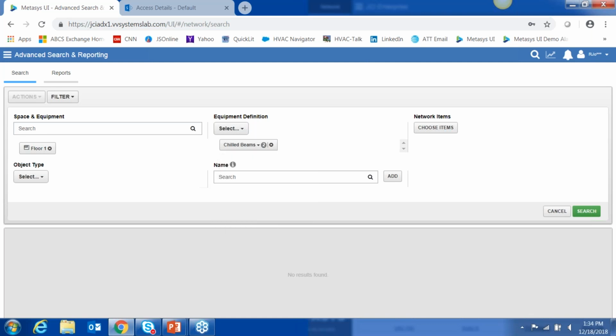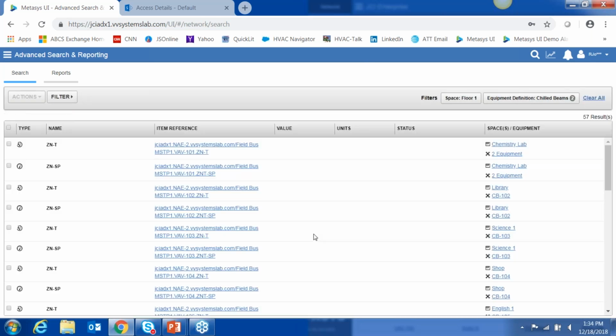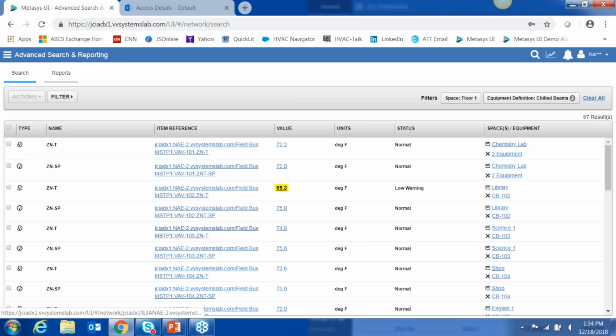Simply by selecting those filters and clicking the search button, a table quickly appears showing the requested information: the point name, the Metasys reference number—which if you're a savvy operator might be a little breadcrumb trail back to your old way of thinking—and the value of the point. If it's in a non-normal status, there'll be a color code indicating maybe an override, above a limit, or out of service. In this case, it's in a low warning state.